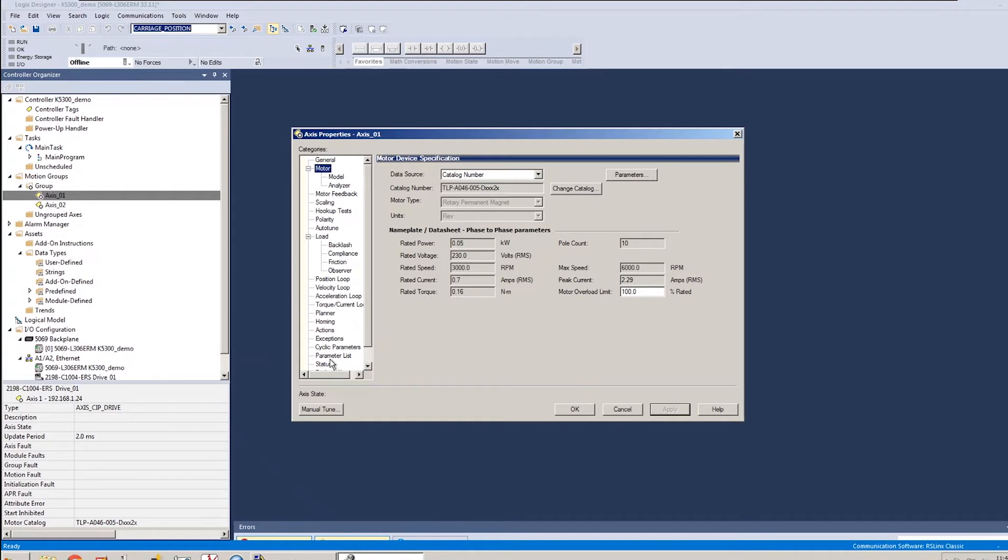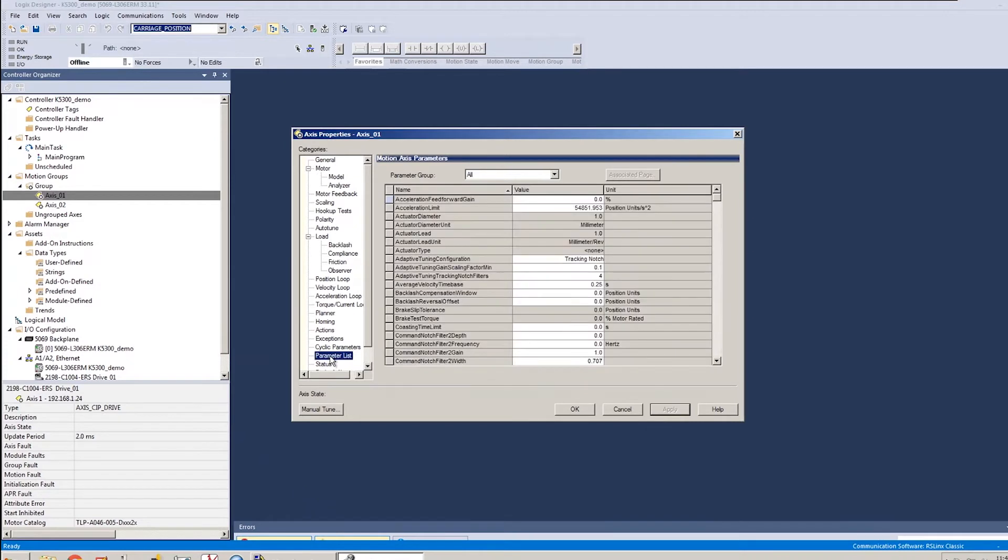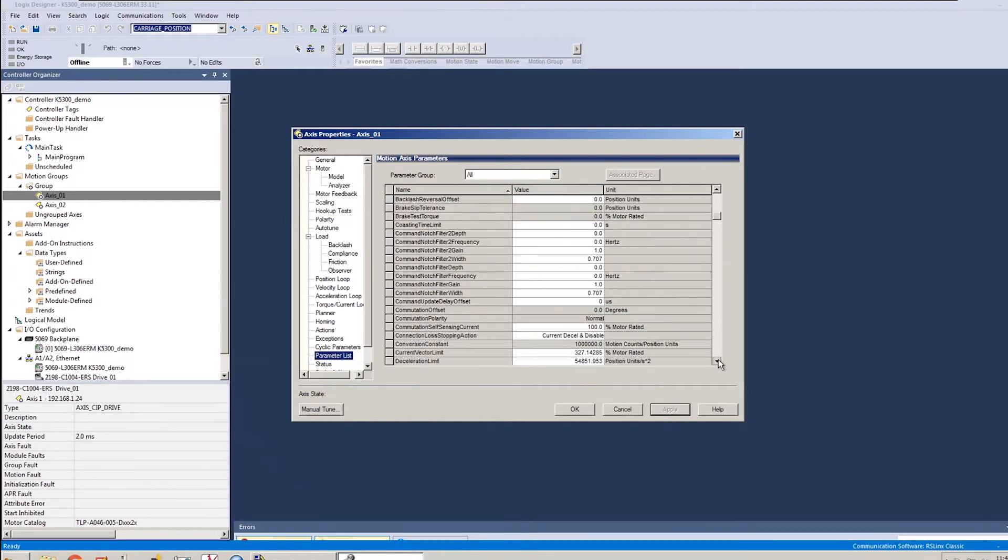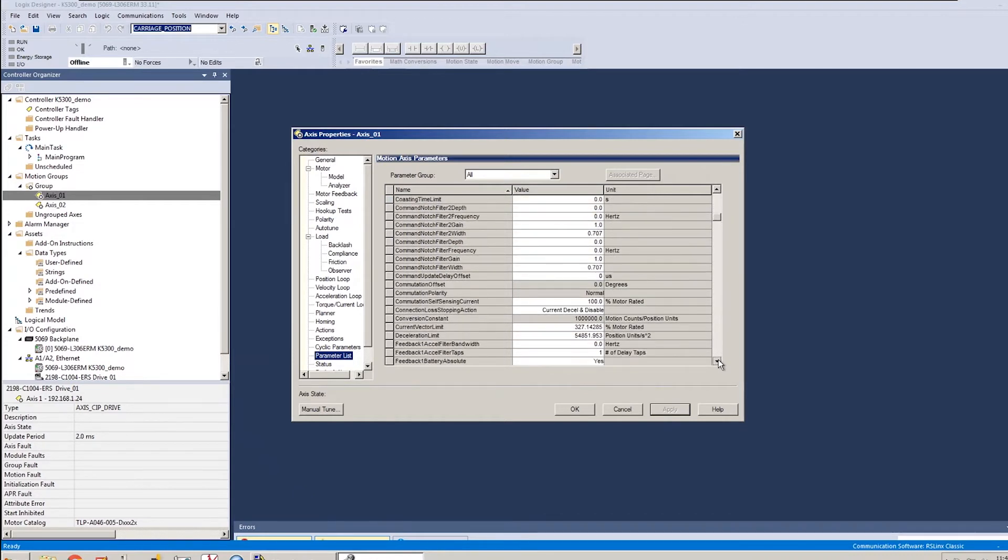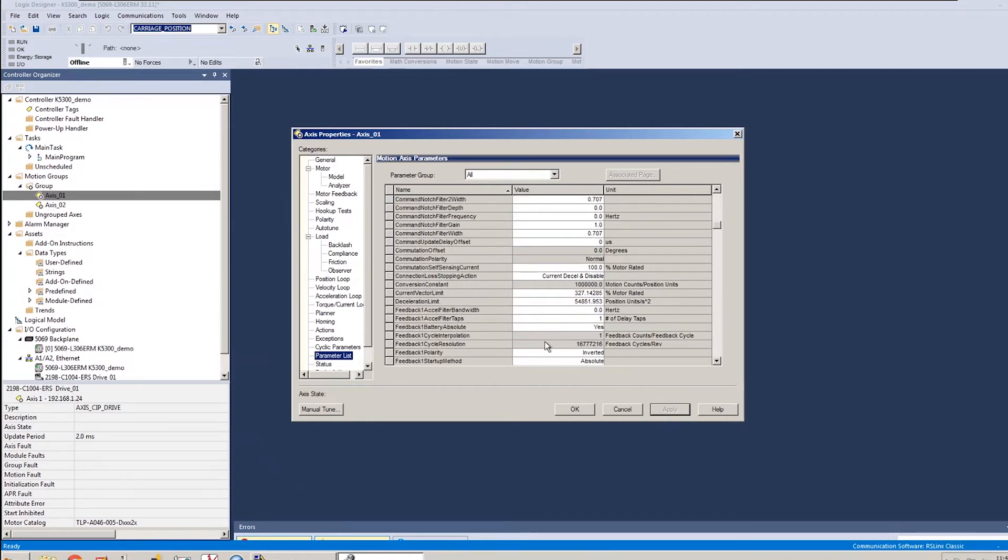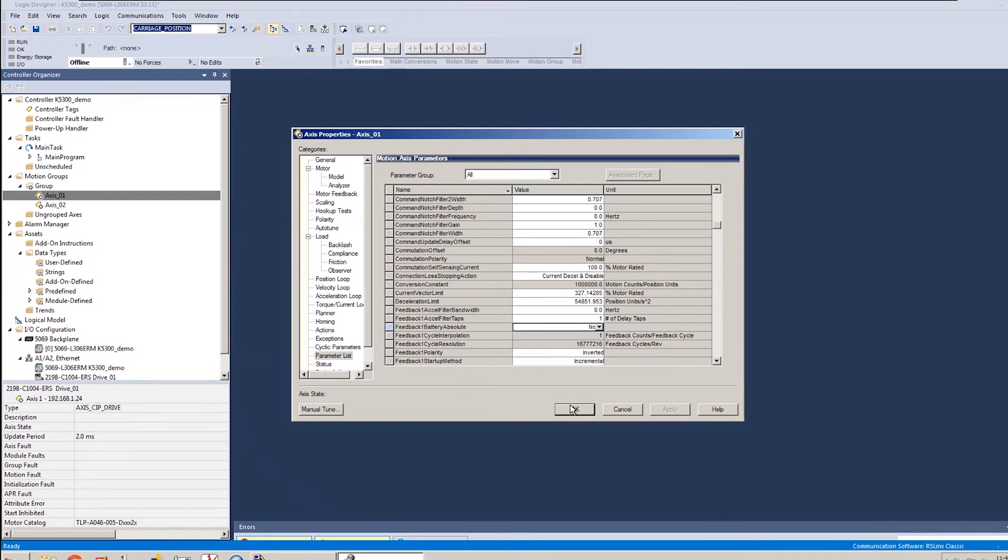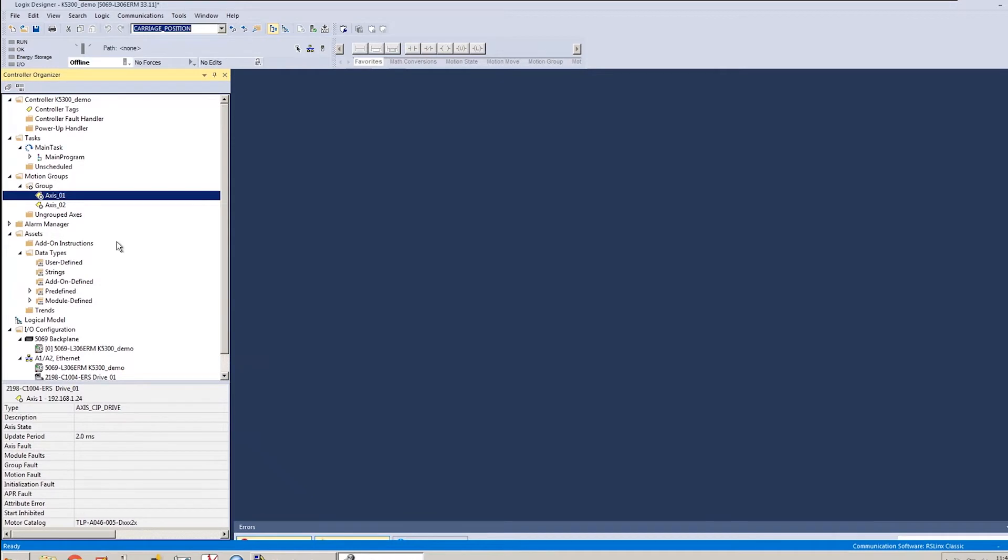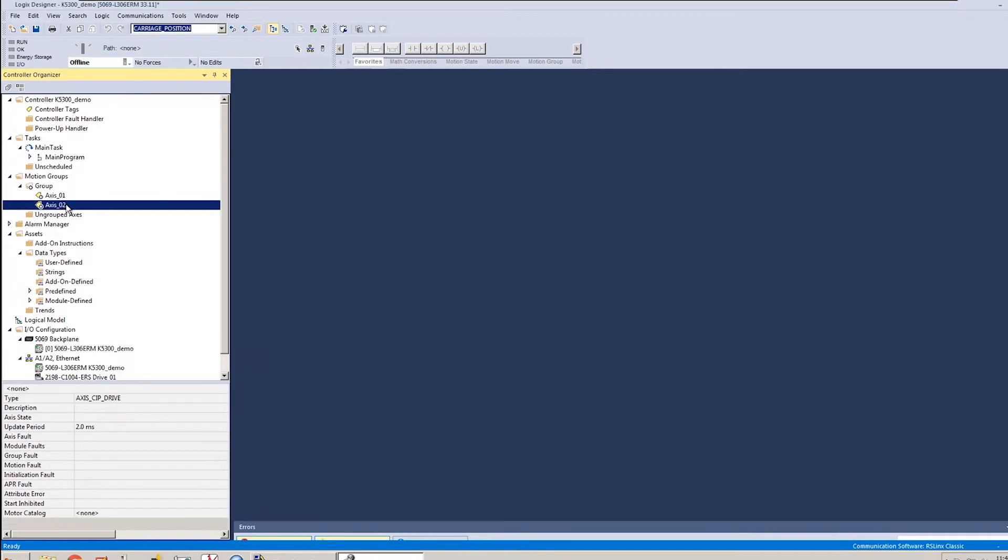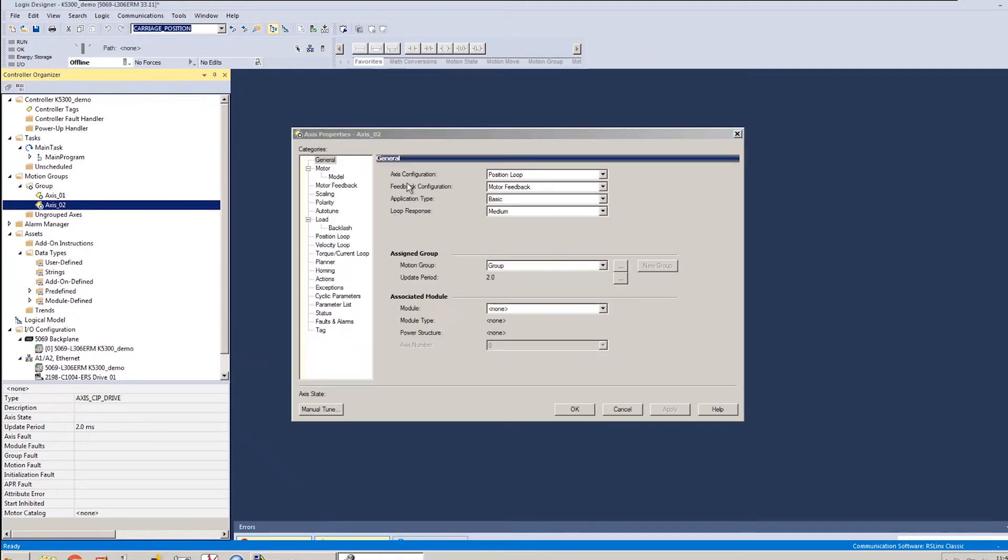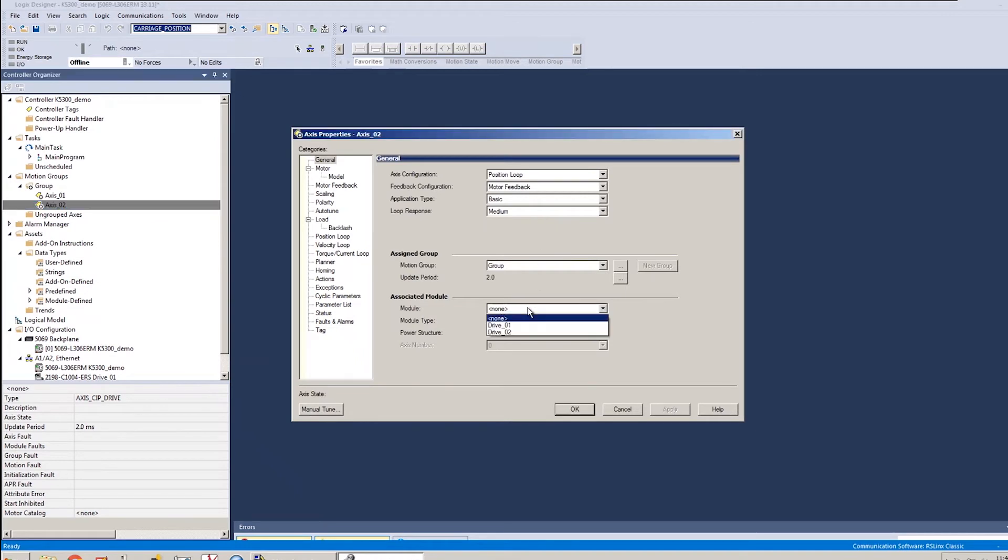And there is one other change that I'm going to make on my parameter list tab. And whether you do this or not would depend on if you're using the battery backed feedback. In my case, I am not using the battery backed feedback. So I want to set my battery absolute parameter to no. And those will be the settings that I need to put in place just in order to get this axis spinning. Obviously, I could do tuning and other things from there to improve the performance, but just for the sake of this demo, we're going to keep it simple and just do the bare minimum to get it up and running.